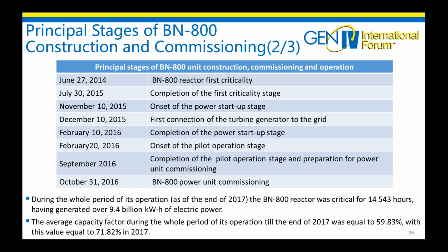In October 2016, BN-800 power unit commissioning. During the whole period of its operation, the BN-800 reactor was critical for 14,543 hours, having generated over 9.4 billion kilowatt hours of electrical power. The average capacity factor during the whole period of its operation till the end of 2017 was equal to 59.83%, with this value equal to 71.82% in 2017.